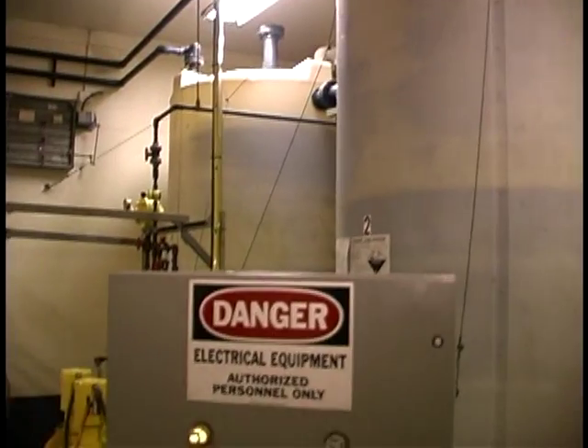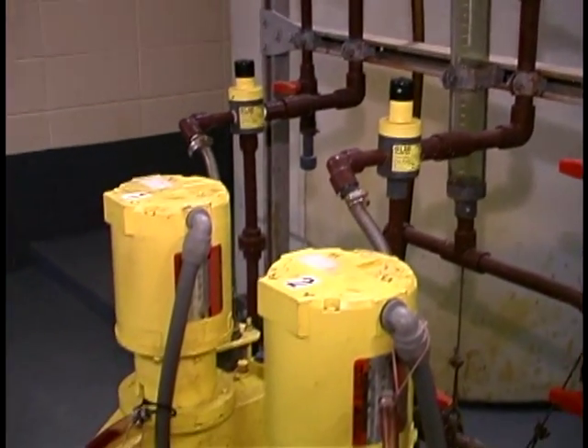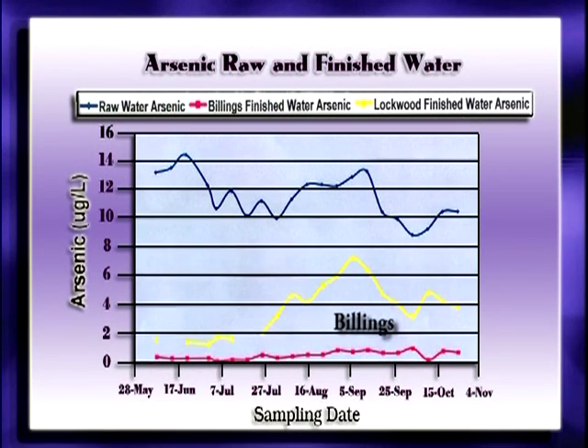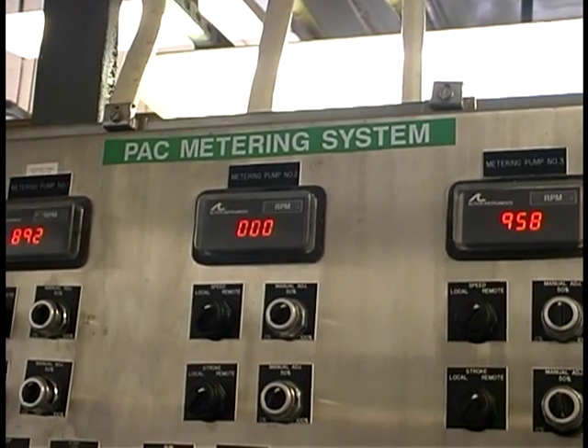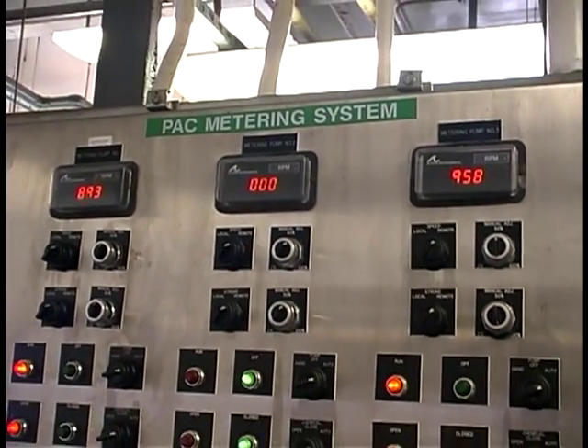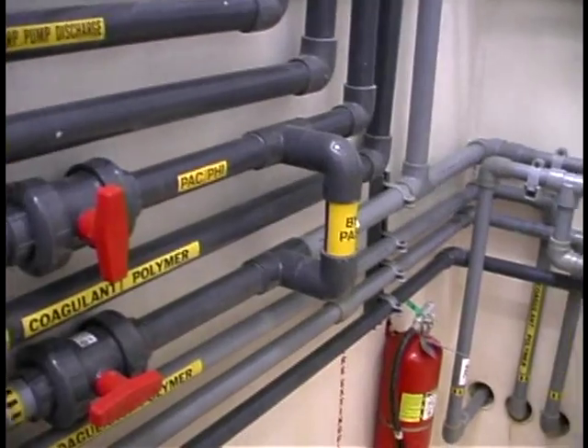The Lockwood Water District continued to use alum as a coagulant, providing an excellent full-scale comparison between aluminum and ferric-based coagulants. Lockwood treated with aluminum sulfate and polymers and typically achieved roughly 50% arsenic removal. As seen on the graph, Billings' finished water arsenic concentration was consistently below the detection level — less than 2 micrograms per liter — while alum at the Lockwood plant removed significantly less arsenic. Billings has since converted from ferric chloride to an aluminum polymer blend to reduce corrosion problems attributed to ferric chloride.